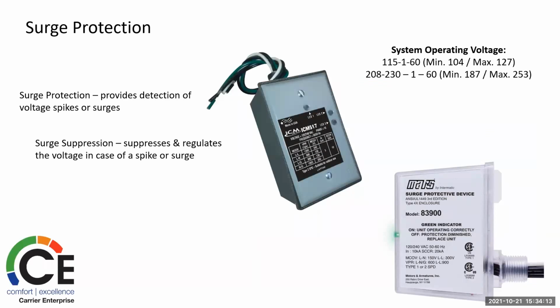Surge protection. Some places have high voltage problems due to brownouts, fluctuating voltages, frequent power outages. We do recommend that you install this surge protector. This does not protect against low voltage. So if your voltage is just dropping down to, I believe it's 197, 193 volts, this is not going to pick that up. But these ductless units are very sensitive to voltage.